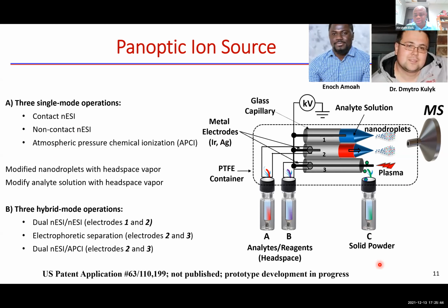And then if you had a solid sample or even a volatile species, and you wanted to do APCI, you can apply 4 kilovolts to this electrode number 3, and a small plasma will be generated here, and you can do an APCI from this vapor or from the solid. I have movies, I didn't add it to this slide. I have movies showing that in the presence of the voltage, if you have a powder without any physical contact, you could actually release the particles of the powder into air and now ionize the particles using the plasma. I think I have one data for this for you.